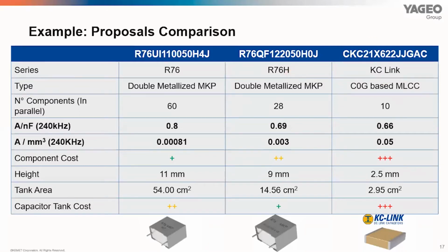We know such high power resonance systems usually comprise large capacitor banks, many in parallel and sometimes many in series. Interestingly, we often see capacitors in series just to lower the overall capacitance, because we need to be accurate when tuning our capacitors and cannot over-dimension our capacitor bank.